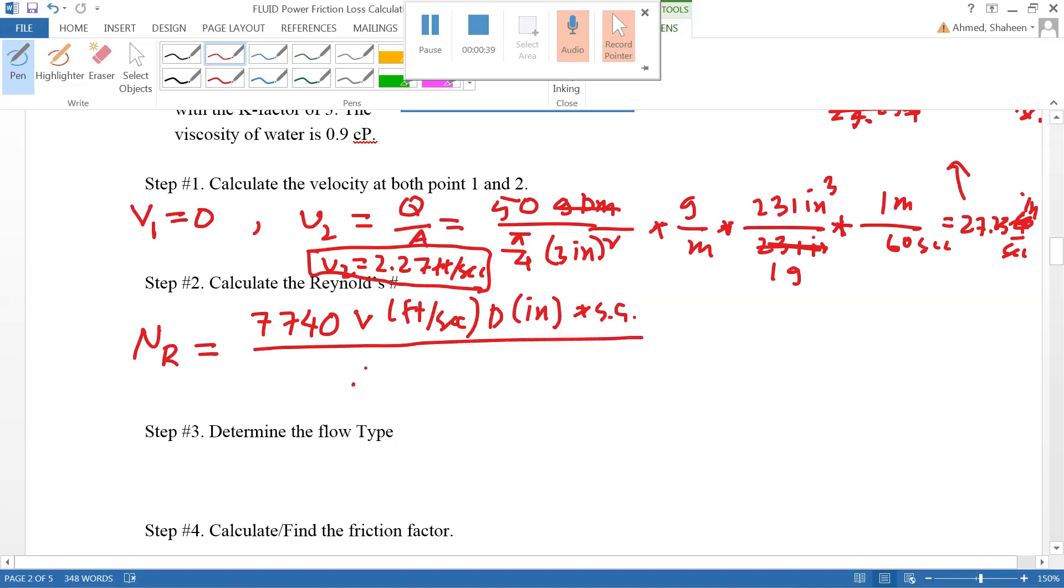The dynamic viscosity is in centipoise. If we input all these values here: 7740 times the velocity of 2.27 feet per second, times the diameter of 3 inches, times the specific gravity...